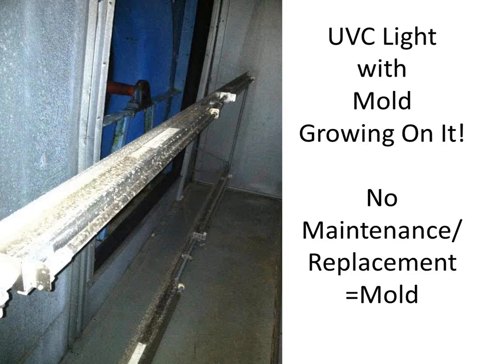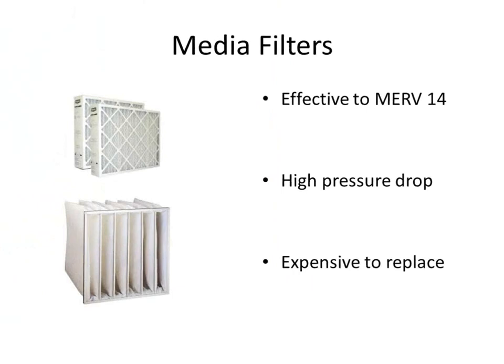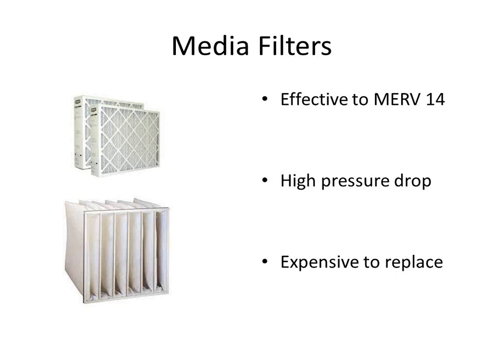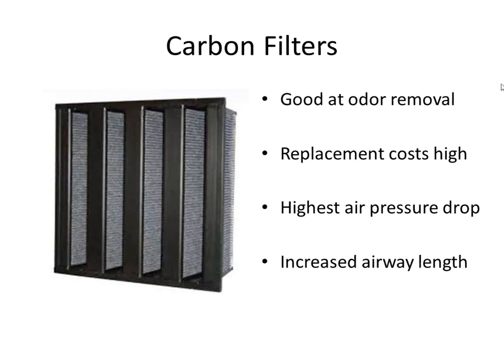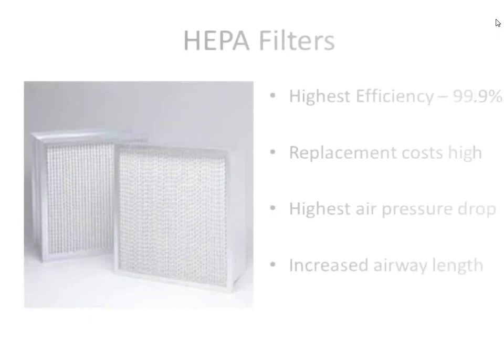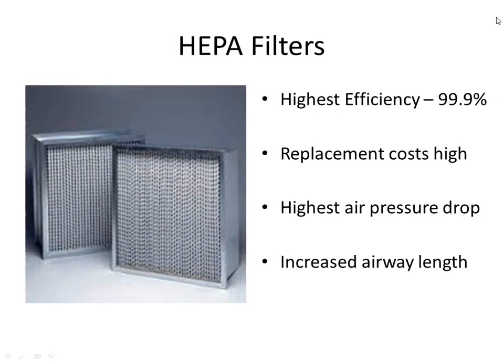Media filters are effective to MERV-14, but the downsides are they have a higher pressure drop, and they're expensive to replace. These have to be replaced every 3 to 6 months. Carbon filters are very good at odor removal, but the replacement cost is high, and of course they have the highest pressure drop. Also, one of the things is increased airway length. HEPA filters have the highest efficiency, but the replacement costs are very high, very high pressure drop, and also increased air length.